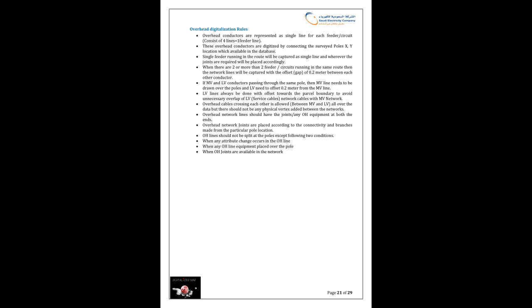If MV and LV conductors pass through the same pole, then the MV line needs to be drawn over the poles and the LV needs to be offset 0.2 meter from the MV line. LV lines should always be offset towards the parcel boundary to avoid unnecessary overlap of LV, service cables, and network cables with the MV network. Overhead cables crossing each other is allowed between MV and LV all over the data, but there should not be any physical vertex added between the networks.